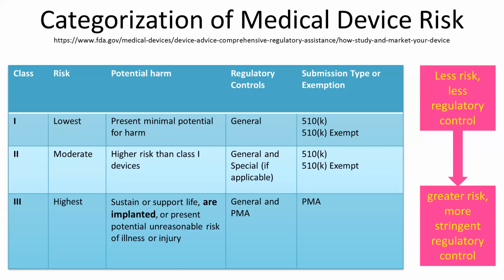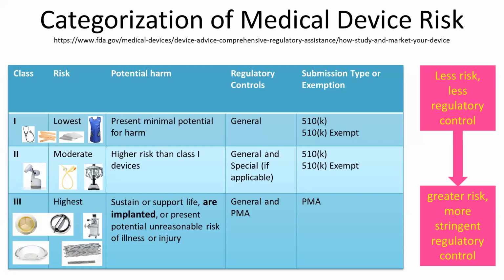And this chart shows the 3 categories of medical device risk. The device classification depends on the intended use of the device and the indications for use. So class 1 is the lowest risk, which presents minimal potential for harm to the patient. Class 2 is moderate risk, which is higher risk than class 1, and due to that risk has a higher level of regulatory control. And class 3 are the greatest risk devices which sustain or support life, can be implanted, or present potential unreasonable risk of injury or illness. And as the risk goes up, the regulatory control of the devices becomes more stringent.